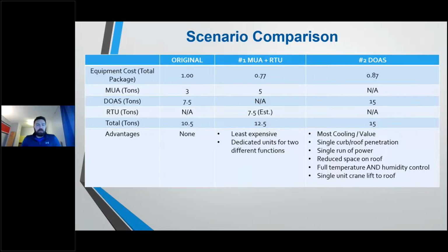So again, three different scenarios. I think it's pretty straightforward, in my opinion. That first scenario, it did work, don't get me wrong, but that DOAS is so underutilized that it's just not the best way to go. The more traditional style is going with a dedicated makeup air fan and a rooftop unit. It's typically going to be your least expensive option, but you're going to give up dehumidification. And then the final option would be to eliminate the rooftop and the makeup air and then get full dehumidification out of the DOAS unit.